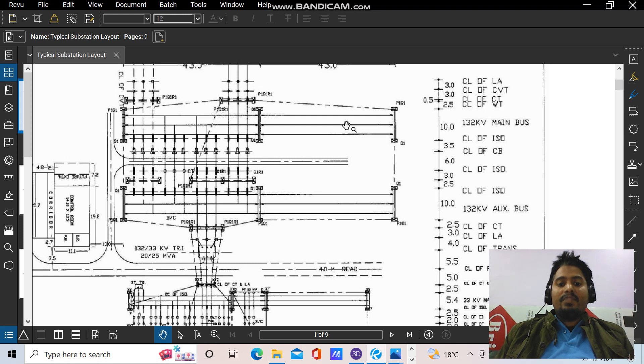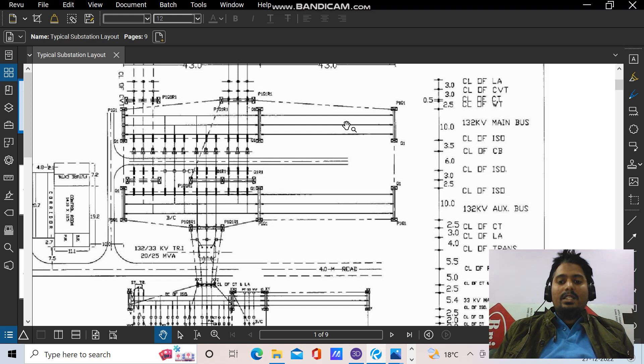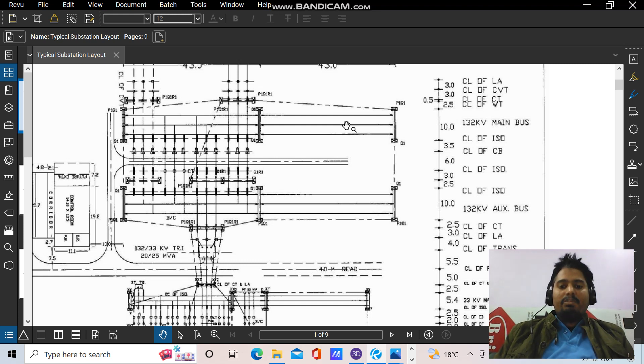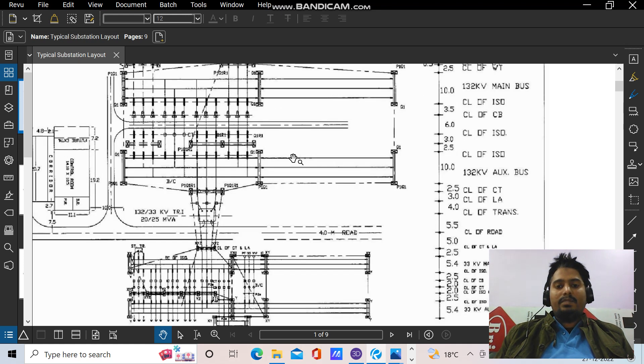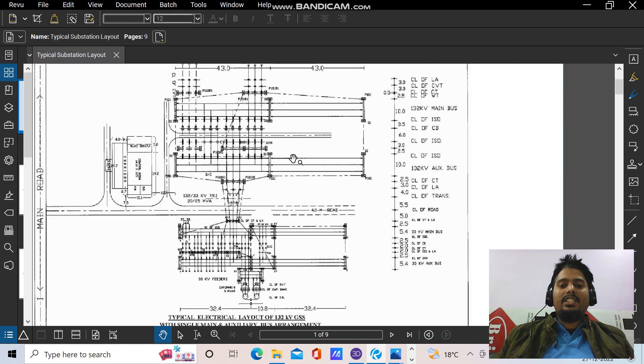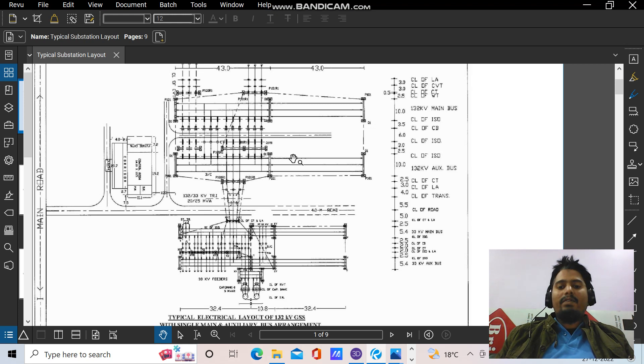Based on the insulation, there are two types of substation. The first is the GIS substation — Gas Insulated Substation — where the entire equipment is within a building. You design a building and place all the GIS equipment inside. The other type is the AIS substation — Air Insulated Substation — which is open to the air, the entire substation is not covered. The GIS substation is a compact kind of substation preferred where land is not available in abundance. Where there is enough land and no such limitation, we can go ahead with AIS substation.